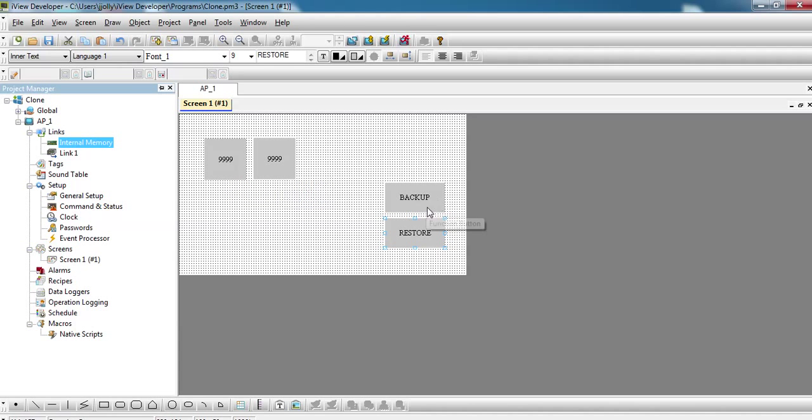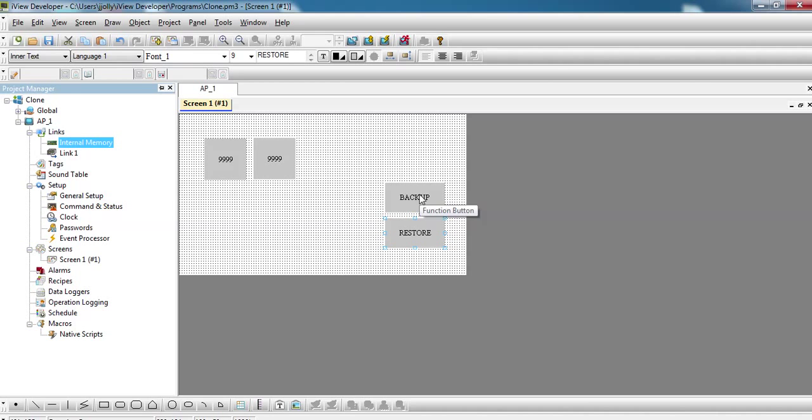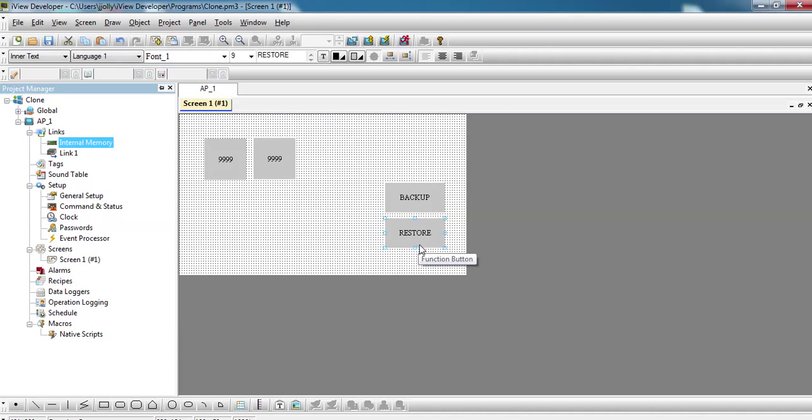And then here we have two functions: backup and restore. This backup function, by pressing it, will be able to actually store a .d80 file wherein you'll be able to have all the values in the dollar n registers saved in the memory. The restore function you'll be able to use to download the new program and restore it using this function back into the HMI controller. Thank you for watching this video.